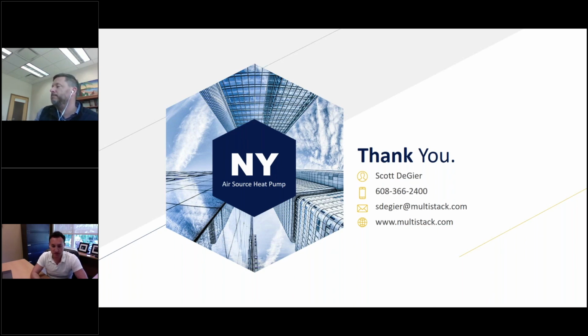Okay, great. So for extreme cold outside air temperature conditions, wouldn't one want to consider electric resistance auxiliary heating? Yeah, I guess it comes down to there being multiple factors that go into anytime you design any building or any system. I certainly have seen electric resistance, depending on where you're at, that could be duct heaters, it could be in air handling units, it could be electric boilers as a backup. It really comes down to how you are designing your infrastructure and what the design criteria are. But like I said before, we have the range of temperature at which the air source heat pump needs to operate. The New York climate is within that range.